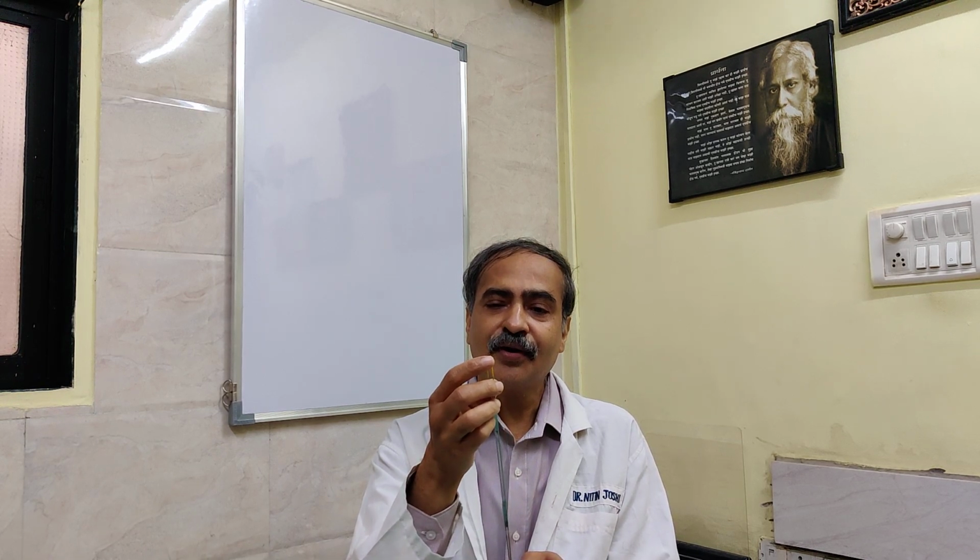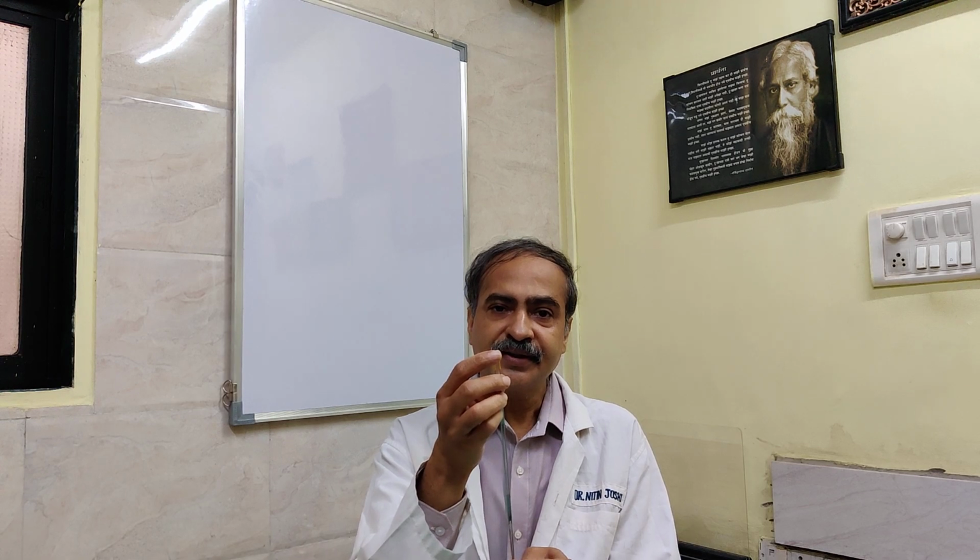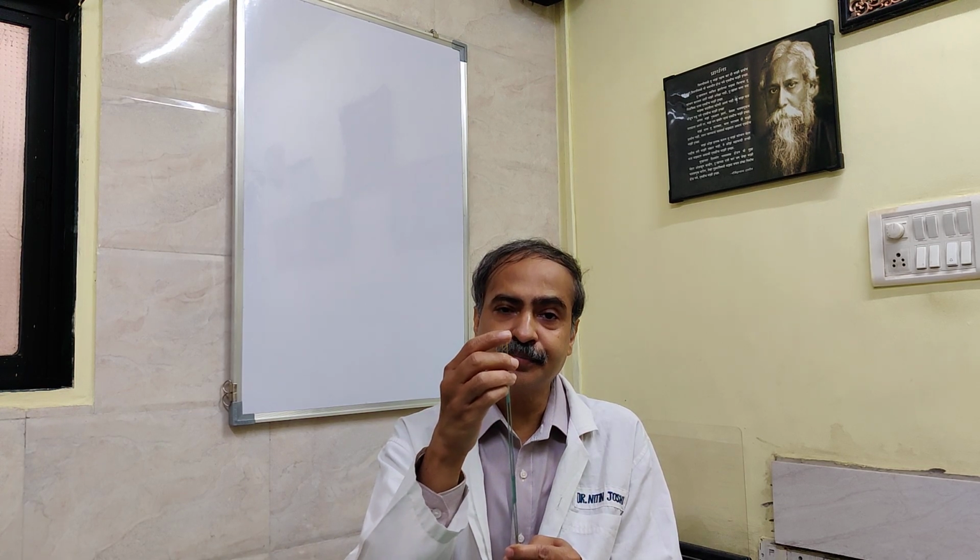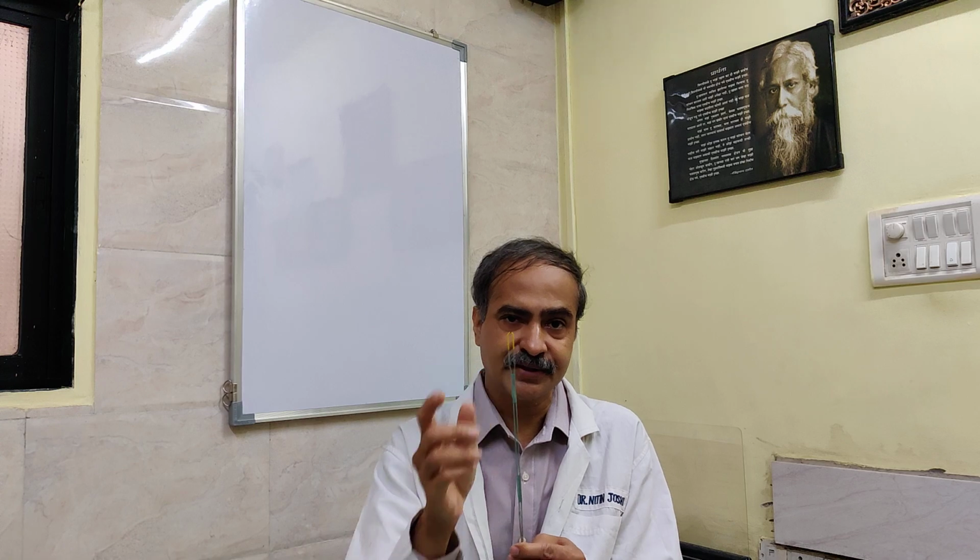Now since it has got a hook or knife, in case of introduction of the resectoscope without obturator, if it is not available, then you can introduce it by mounting the loop to the working element, but you should never introduce the resectoscope sheath even if you want to do the bladder neck incision only. This is because it will be protruding and will damage the urethra.